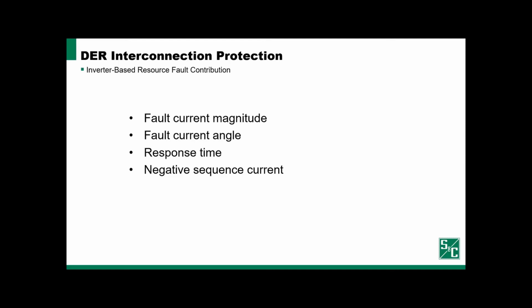So you can see several of these factors are quite different and unique when we integrate inverters and consider how they will contribute to faults, especially as they are displacing existing conventional rotating machines. They'll drive, on net, a reduced fault current throughout the power system.